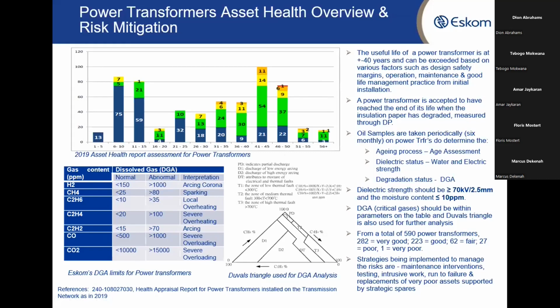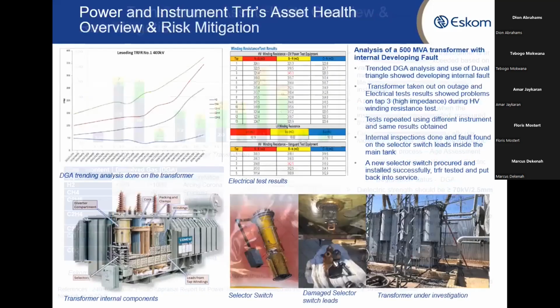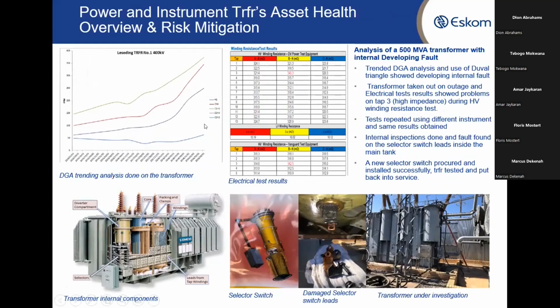So the strategies for management of these assets, transformers, is to do maintenance, make sure that we test them, do some intrusive work, and in some instances, run to failure with a strong strategic spare as a supporting measure. A typical example of where a failure was prevented: you can see here, we had a transformer that had a DGA that was increasing, and one of the engineers that we're working together with detected this and applied the concept that I've shared in the previous slide.